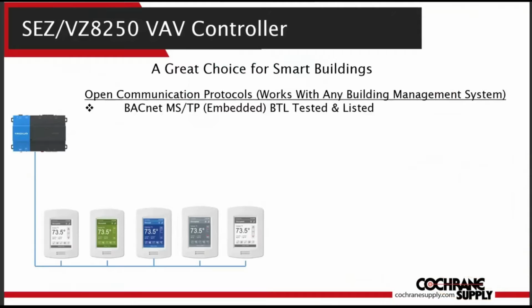Communication options available: the 8250 room controllers are a great choice for all the smart building construction and retrofitting going on these days. Onboard time clock and schedule. Room controller has BACnet MSTP communications. Devices are BACnet Testing Laboratories tested and listed. There's around 500 points or so in each controller that can be read or written to by virtually every BACnet supervisory system on the market.